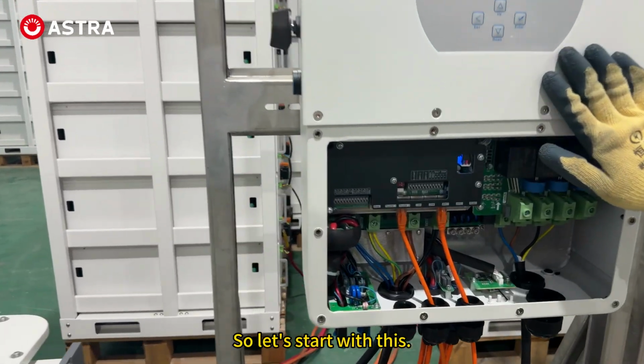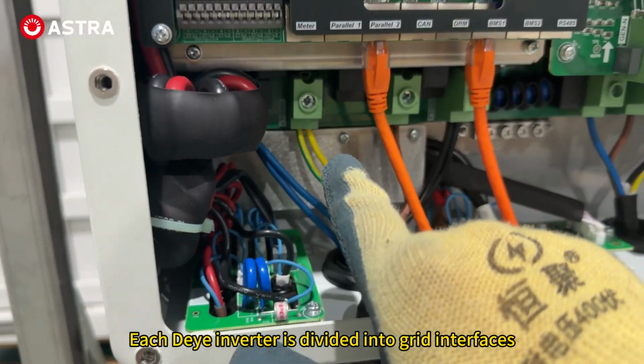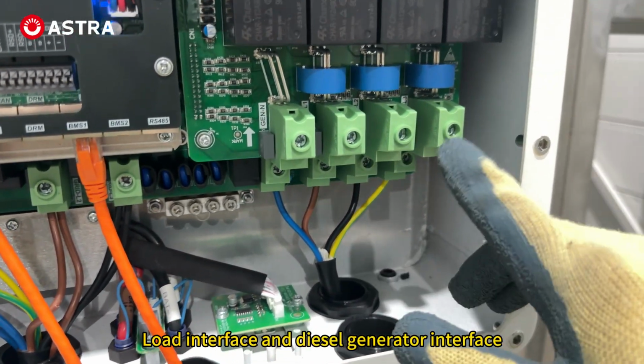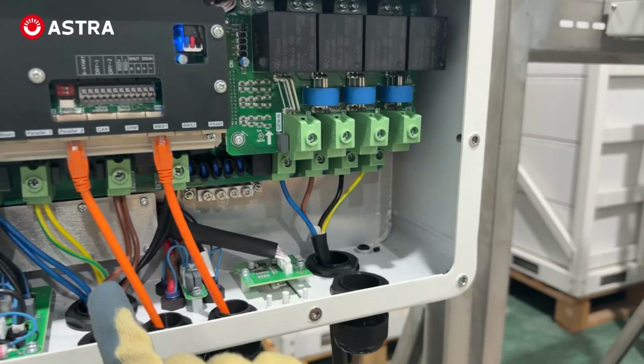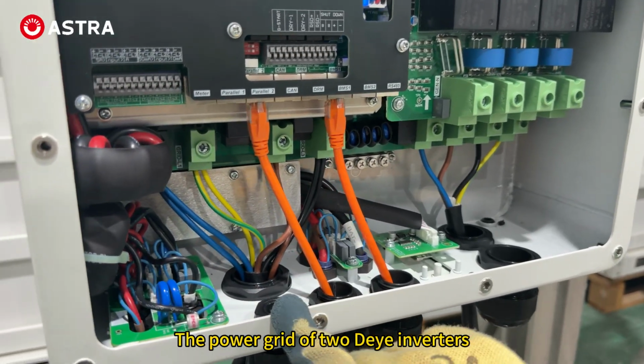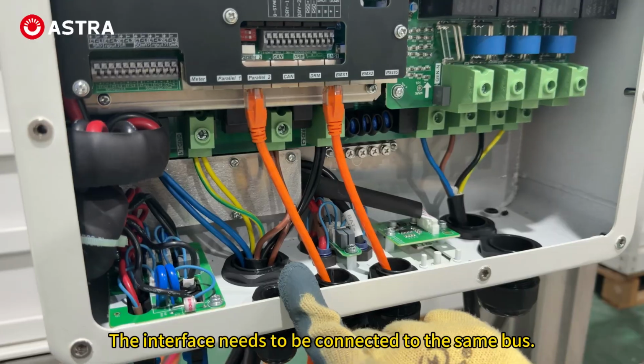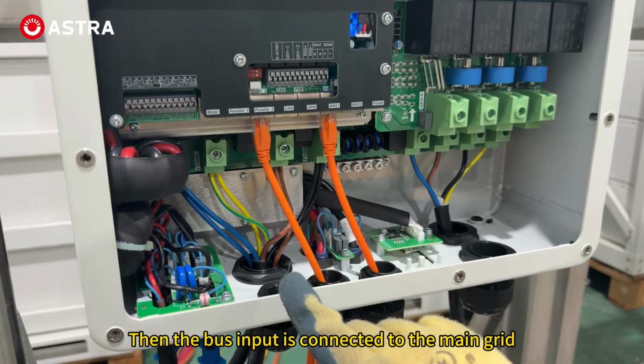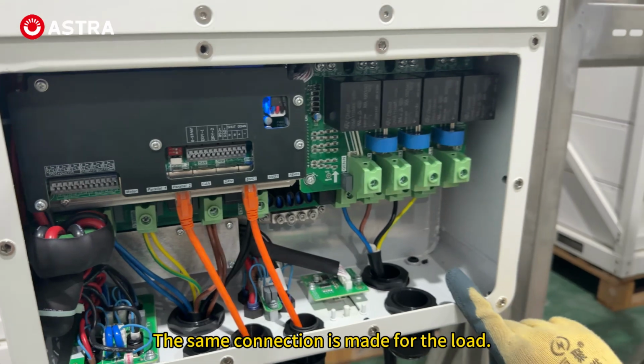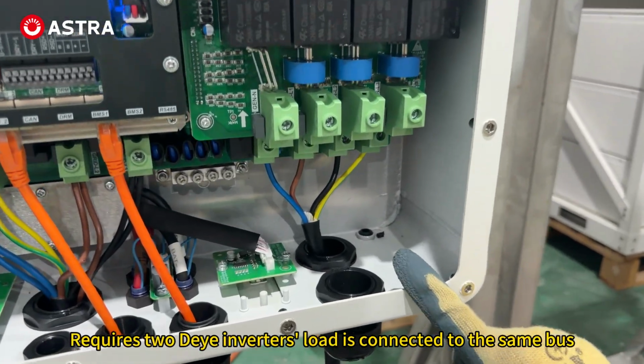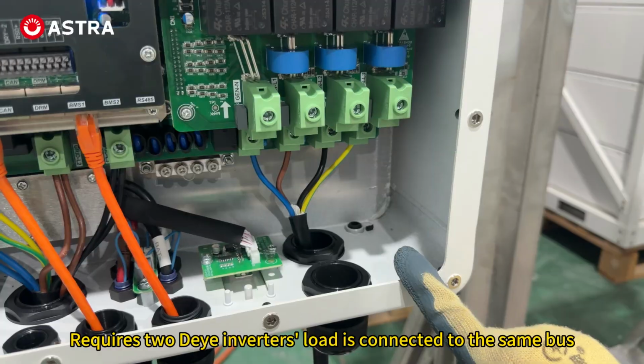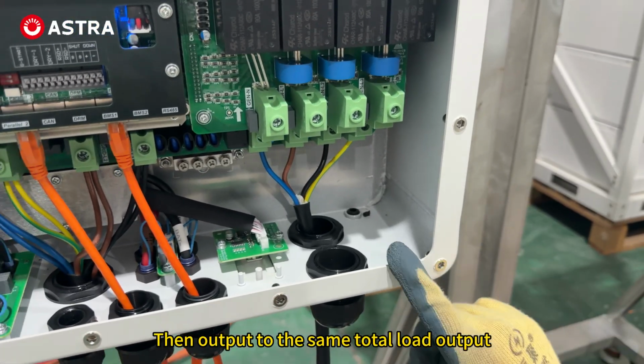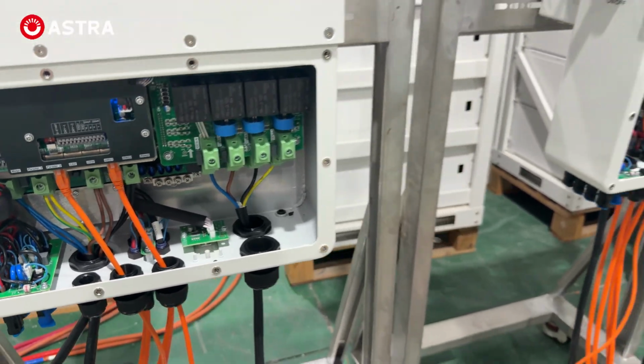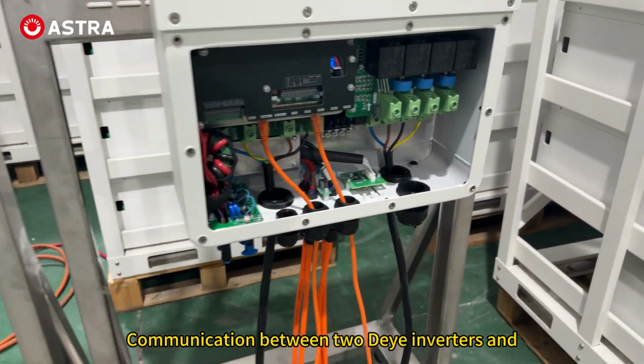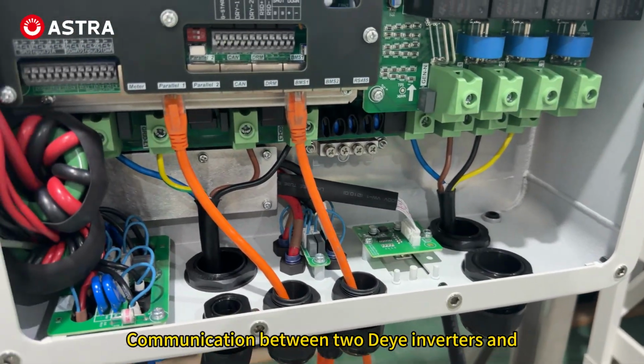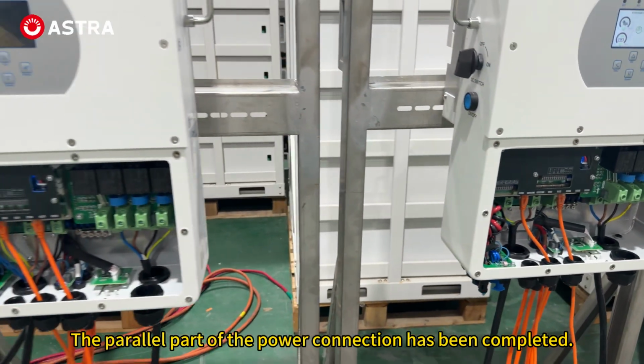So let's start with this. Each inverter is divided into grid interface, load interface and diesel generator interface. The grid interfaces of the 2 inverters need to be connected to the same bus. Then the bus input is connected to the main grid. The same connection is made for the load. The 2 inverters' loads are connected to the same bus. Then output to the same total load output. Communication between the inverters and the parallel part of the power connection has been completed.